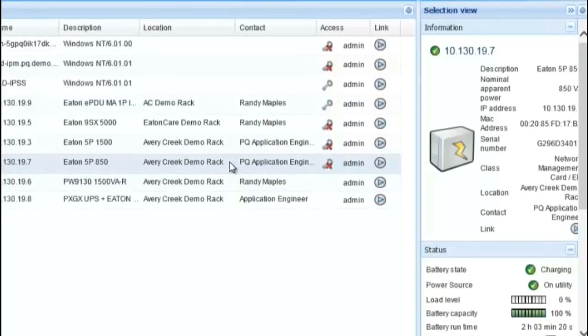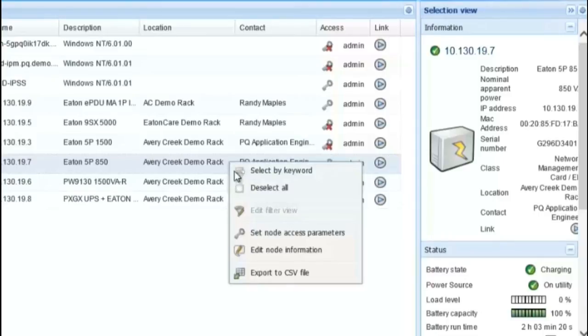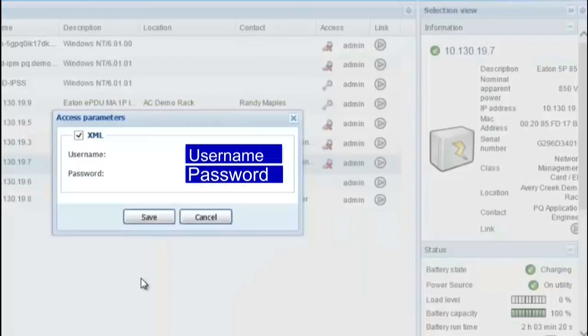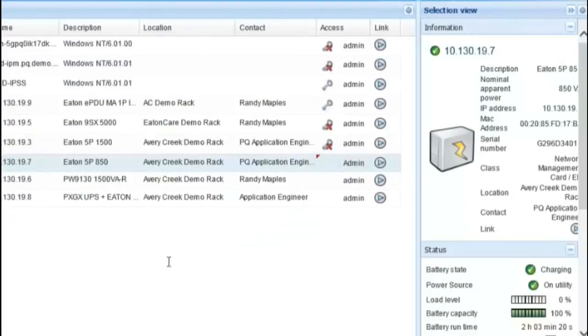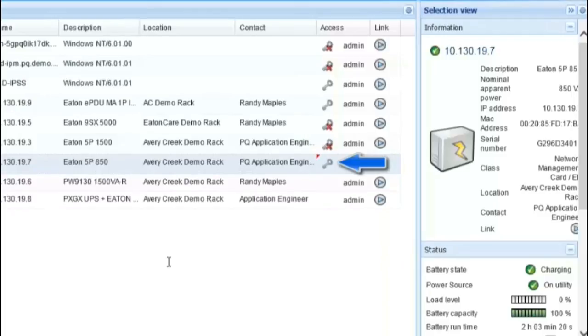In order to correct issues with the linkage, right-click on the node that you want to correct and click the option for Set Node Access Parameter. Enter the username and password for the nodes. Click Save. The node list will now display the key icon without the X in order to illustrate that access has been enabled.